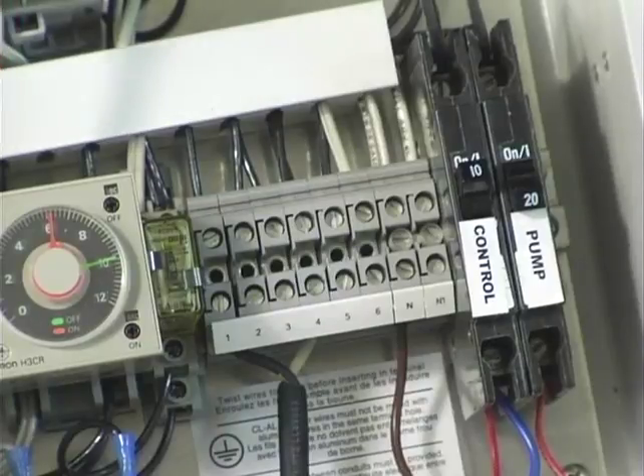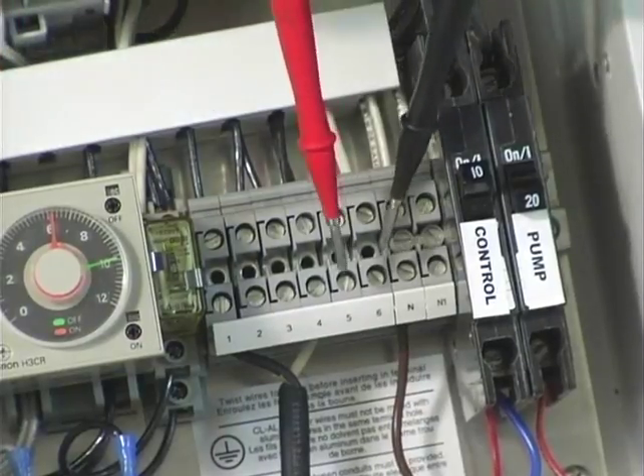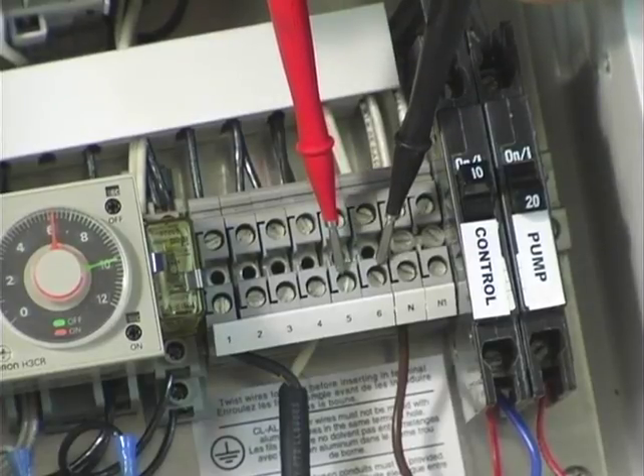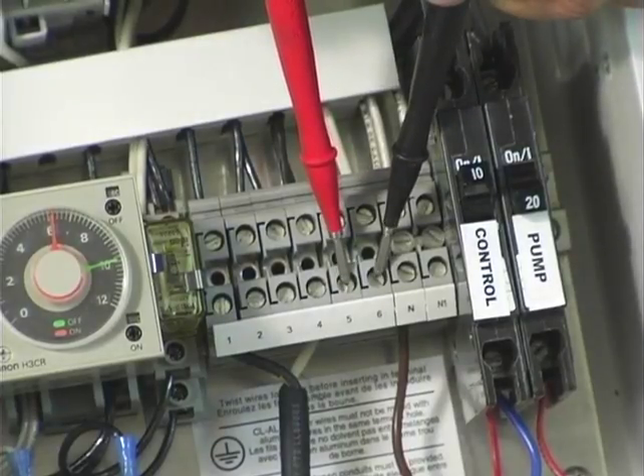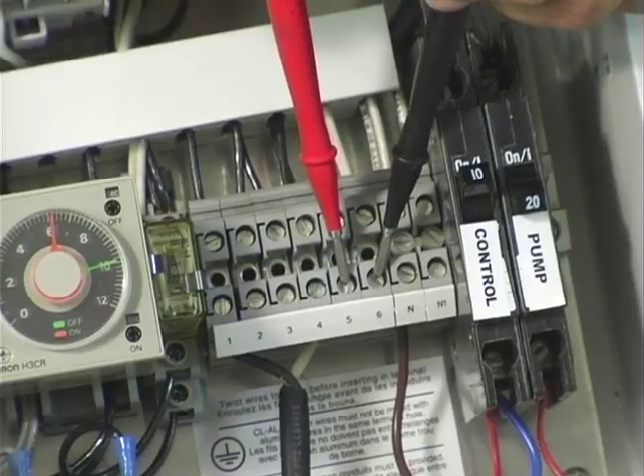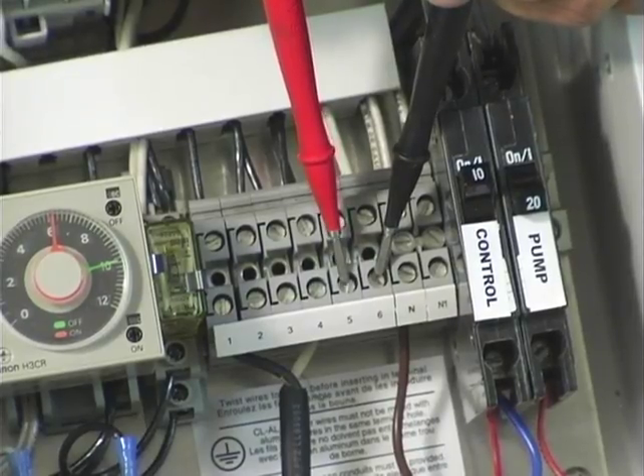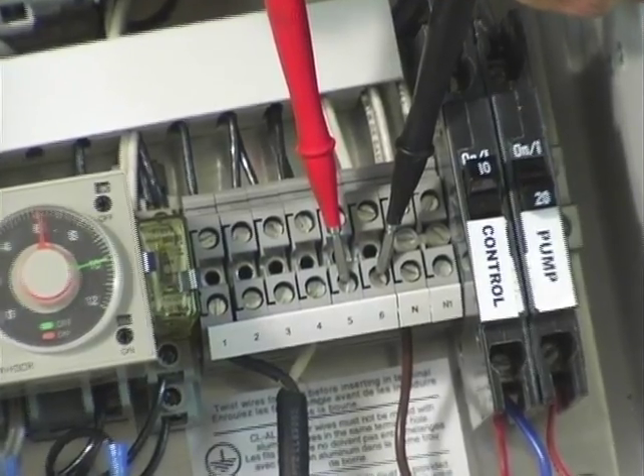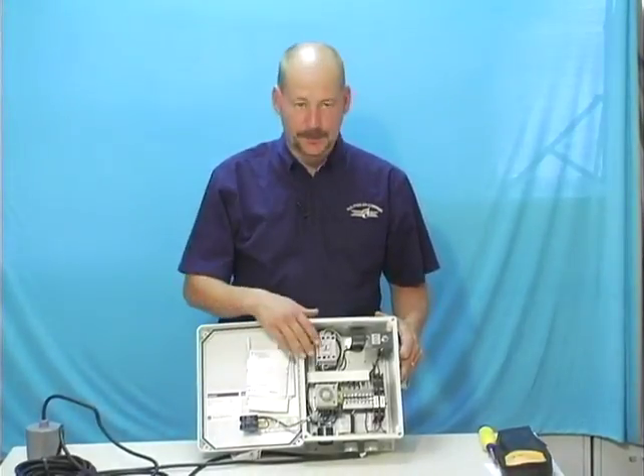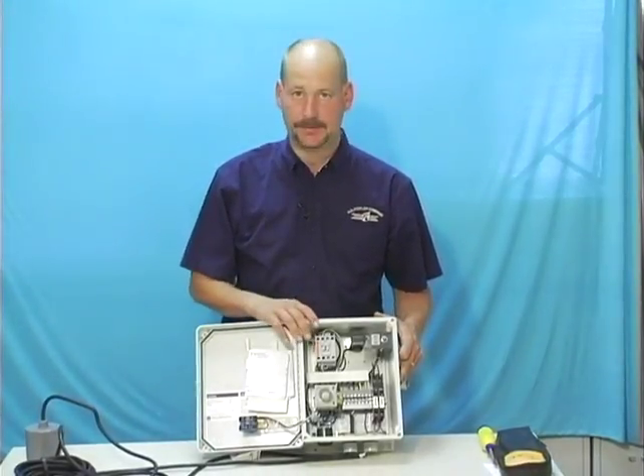When the motor contactor engages, it should be sending electricity out to terminals 5 and 6. And that is our pump leads. What we'll do is we'll check for voltage on 5 and 6 to see if we have 120 volts coming through the system. We've been working on this control panel for a while and we just can't quite figure out what's going on with it.